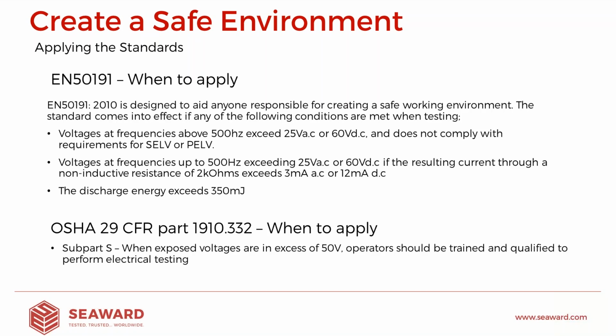There's also the point of what's deemed a safe and good test. In many standards for manufacturing of equipment, if we take, for example, the lighting standard, it actually calls for a maximum pass limit of 5 milliamps when performing a 1500 volt AC hypot test. So we already know that between that level of safety and the level of pass or fail for that particular product, we've got a 2 milliamp window. So we should all automatically be thinking that we definitely need to be performing this test because our voltage is at 1500 volts and our pass limit is 5 milliamps.